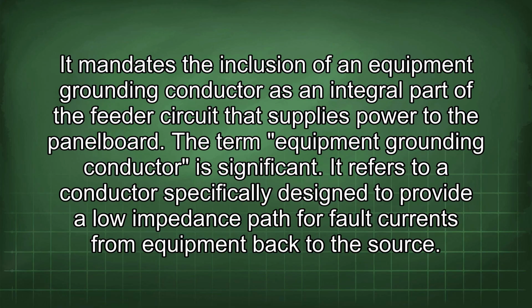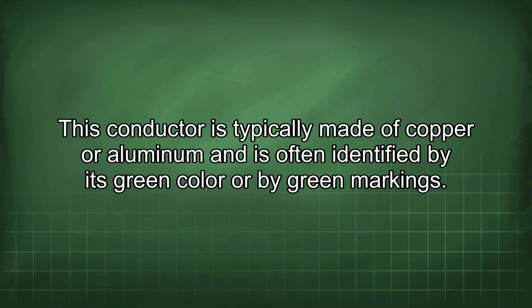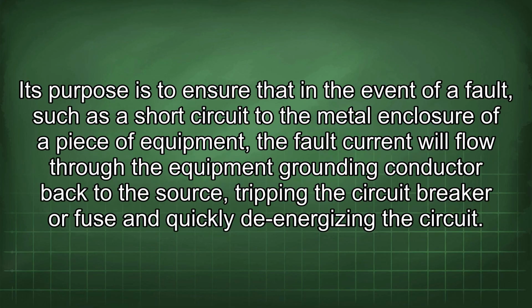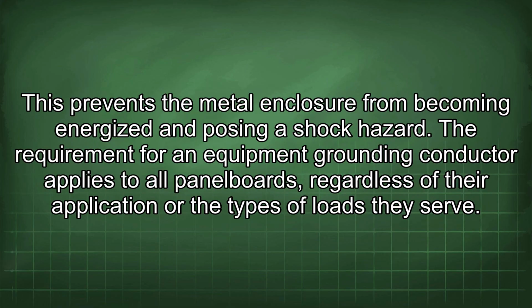It refers to a conductor specifically designed to provide a low impedance path for fault currents from equipment back to the source. This conductor is typically made of copper or aluminum and is often identified by its green color or by green markings. Its purpose is to ensure that in the event of a fault, such as a short circuit to the metal enclosure of a piece of equipment, the fault current will flow through the equipment grounding conductor back to the source, tripping the circuit breaker or fuse and quickly de-energizing the circuit. This prevents the metal enclosure from becoming energized and posing a shock hazard.